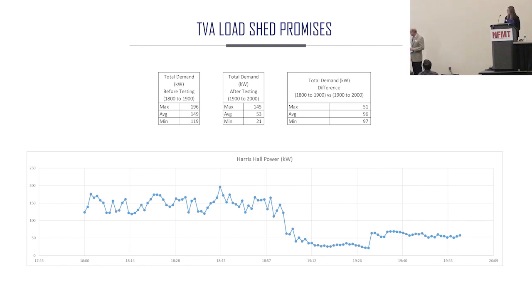I will pop back real quick. So the plot here, what we wanted to highlight, was that you can drop into the load shed, but eventually you're not going to be able to sustain it continuously without incurring a cost of performance, a cost of comfort, or something like that. The equipment eventually is going to say, look, I have to come on if we're going to meet minimum thresholds. So having a good plan, and Kallie will later talk about a decently complex plan, on how to prevent this: we made load shed, but now our system is trying to self out of load to satisfy building loads.